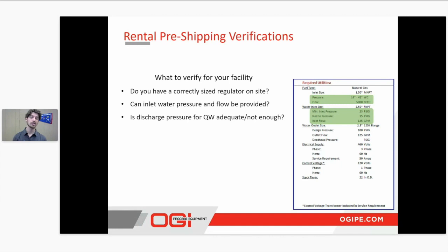Next, the discharge pressure for the QuikWater. Is this going to be adequate for your process? Is it going to be not enough? Will you require a booster pump tacked on to this rental? For this design, we have 100 PSIG at that 125 gallons per minute. If you need, say, 200 going through your piping in your hot water loop, we can go ahead and work on getting the booster pump that you need to supply that extra PSI.